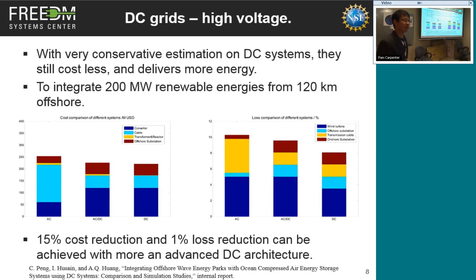AC cables have their problems when it comes to long-distance transmission, mainly because of the reactive power. A lot of reactive power flows in the AC cable, which does not actually contribute to power transmission, but it occupies the available transmission capability of that cable. So you have a cable maybe this big, but you're actually only using a portion of it—that's a waste of copper. The DC system has no problem like this. That's one of the biggest reasons long-distance underground or undersea DC transmission makes sense.